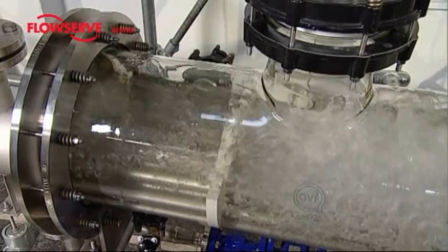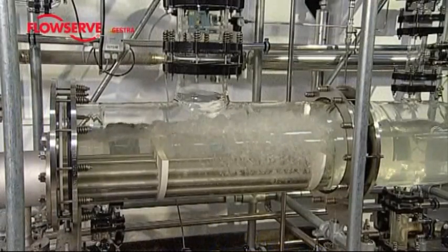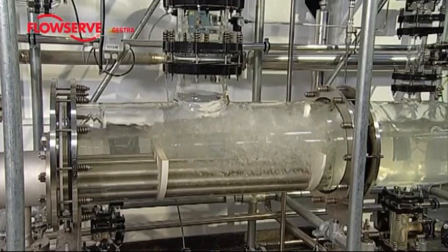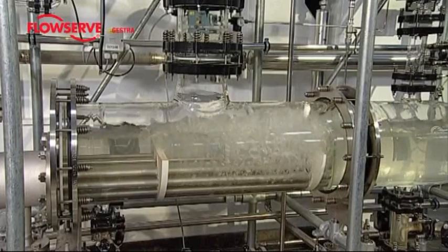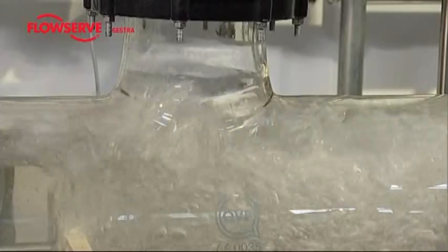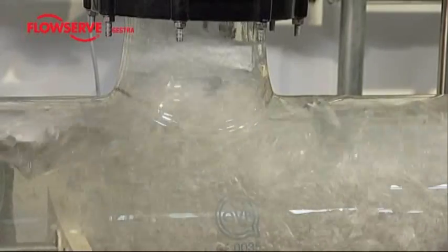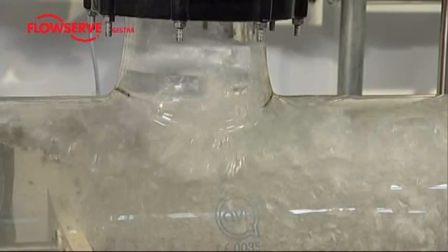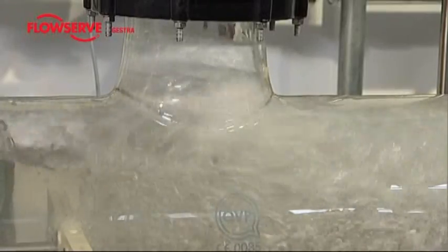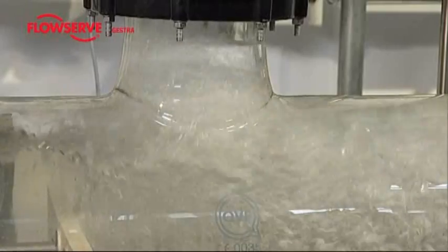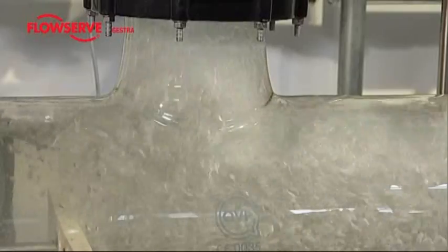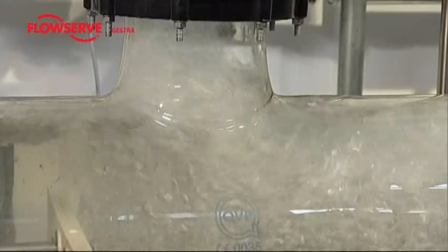More feed water has entered the steam boiler and the filling level has reached 65%. The first droplets shoot up in the steam dome. The steam boiler starts priming. This is a critical moment in the steam process because boiler water with a high conductivity then passes into the steam system. Priming leads to increased corrosion in the entire steam system, with all the consequences in terms of cost. To make matters worse, the steam loses heat because it's mixed with water. A kind of wet steam leaves the steam generator.